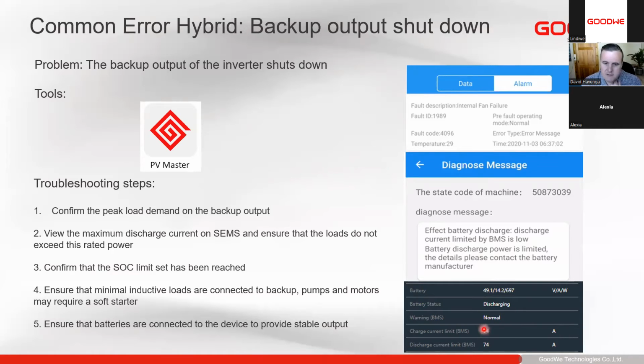So this discharge current limit here. As you'll see, this is a low voltage 48 volt nominal system at 74 amps, so we can know that's roughly 3.4 kilowatts that the customer can run on this inverter. Should it exceed that when the grid's available, it's fine, but when there's only batteries available, the inverter will shut down when we're exceeding the discharge current limit of the batteries.